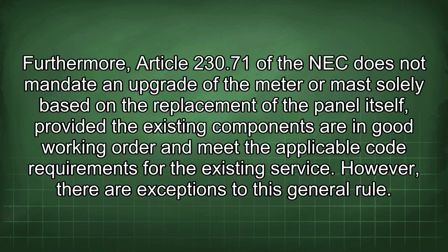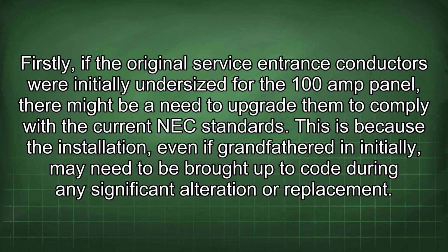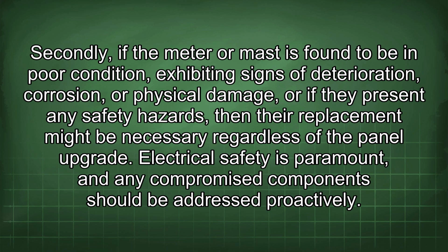However, there are exceptions to this general rule. Firstly, if the original service entrance conductors were initially undersized for the 100 amp panel, there might be a need to upgrade them to comply with the current NEC standards. This is because the installation, even if grandfathered in initially, may need to be brought up to code during any significant alteration or replacement. Secondly, if the meter or mast is found to be in poor condition, exhibiting signs of deterioration, corrosion, or physical damage, or if they present any safety hazards, then the replacement might be necessary regardless of the panel upgrade. Electrical safety is paramount, and any compromised component should be addressed proactively.